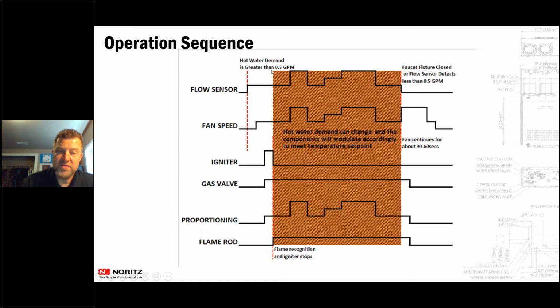Most tankless water heaters need either 0.5 gallon per minute or 0.4 gallon per minute for that unit to operate and fire. With tankless, there's a minimum BTU and a maximum BTU. Most of the units put into Utah are either 180,000 BTUs or 199,000 BTUs, but their minimum BTU could be 18,000, 19,000 BTUs.